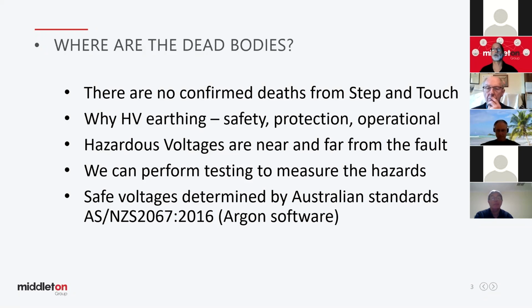We looked at hazardous voltages. They can be near the substation. Quite obviously, you expect to have dangerous voltages around substations, but they can be quite far away from the fault, many hundreds of metres away. The voltages can be transferred along fences or cable sheaths, etc., and appear somewhere else, and again, invisible. But we can perform some testing to measure what these hazards are, and we've also got a whole bunch of standards that determine what the safe voltage is. So that's just a brief overview.